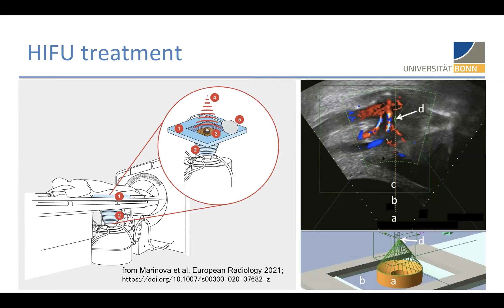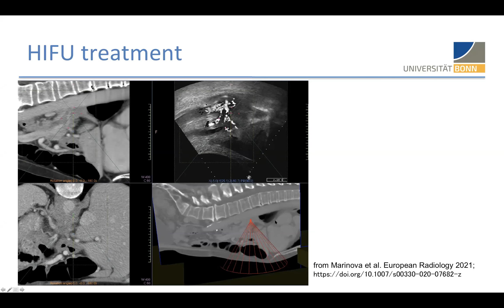Using the auxiliary software, fusion of real-time ultrasound images with CT or MRI images obtained prior to the HIFU treatment can be displayed. The figure shows CT images fused by the software during HIFU. The current ultrasound image of the HIFU device and the calculated projection of the therapeutic ultrasound beam on the CT image are displayed. The focal zone is shown as an oval cigar-shaped area in the tumor. Although this is a nice option, in practice it is rarely needed.